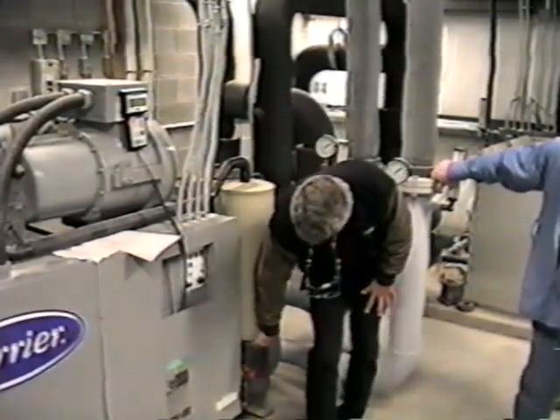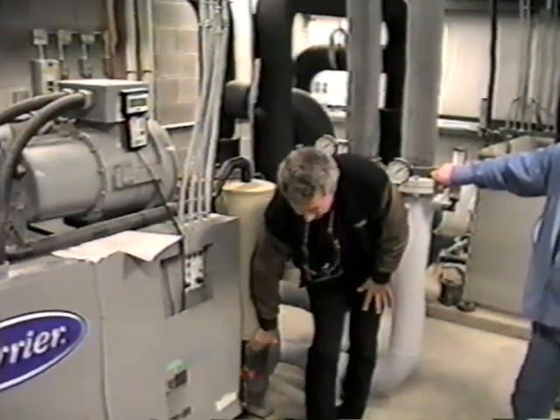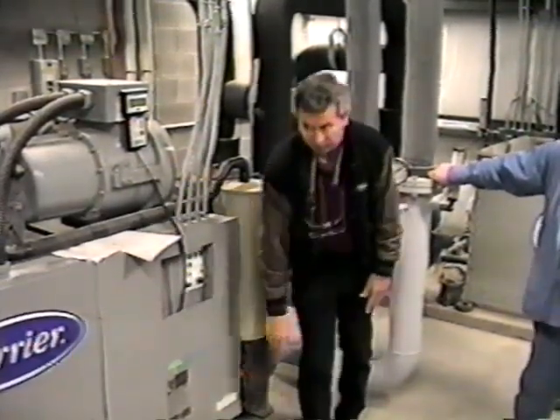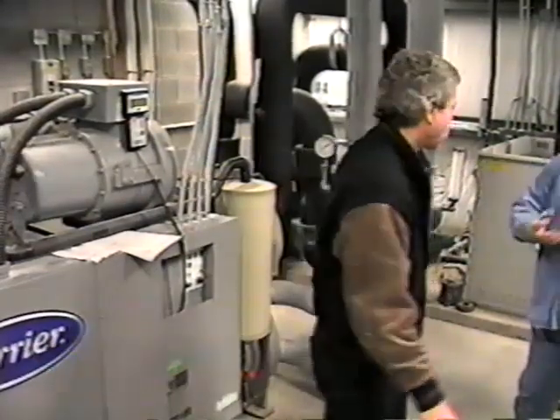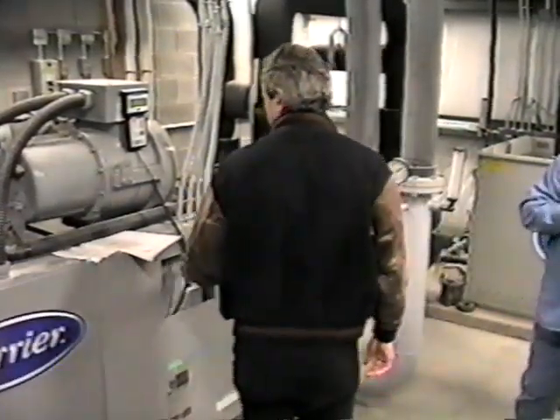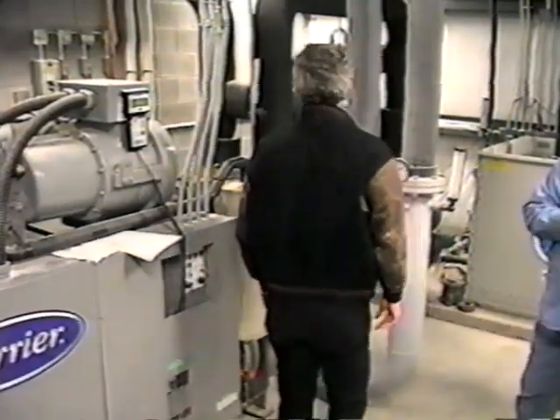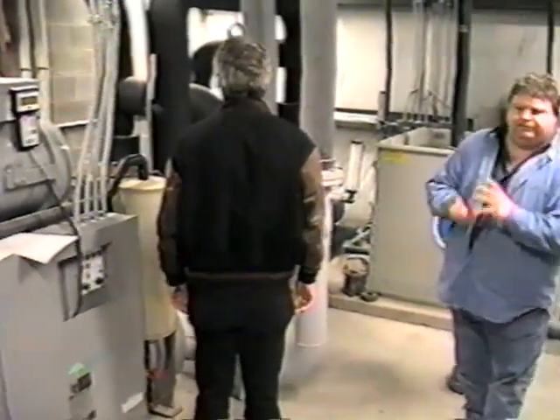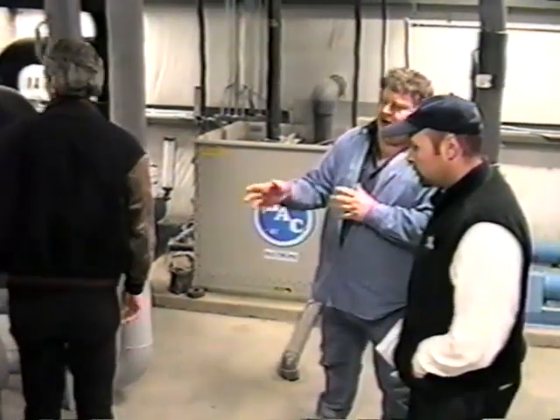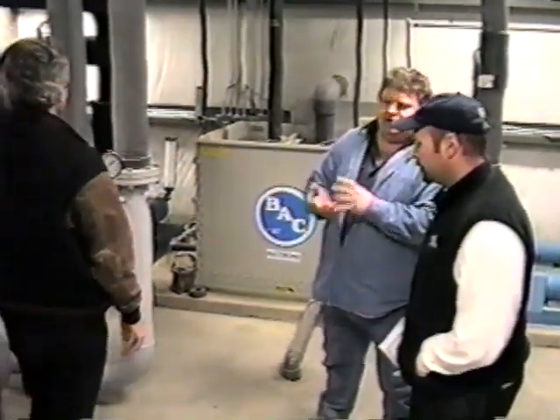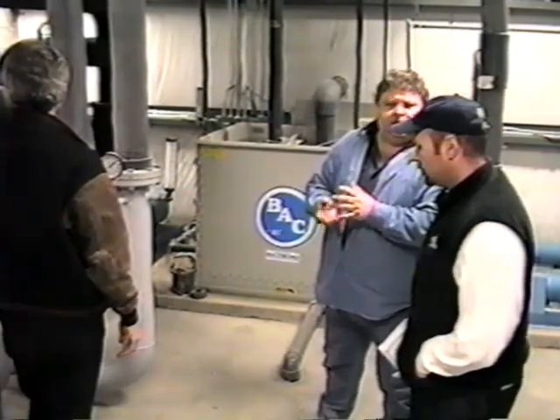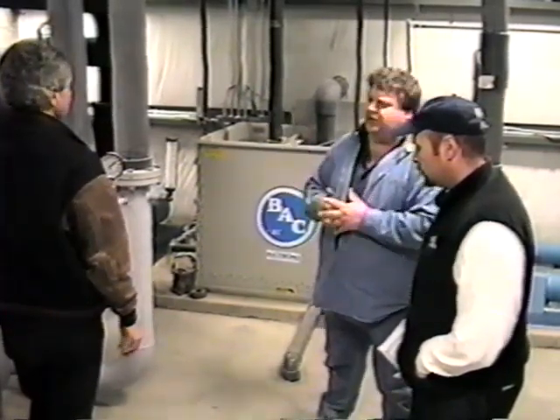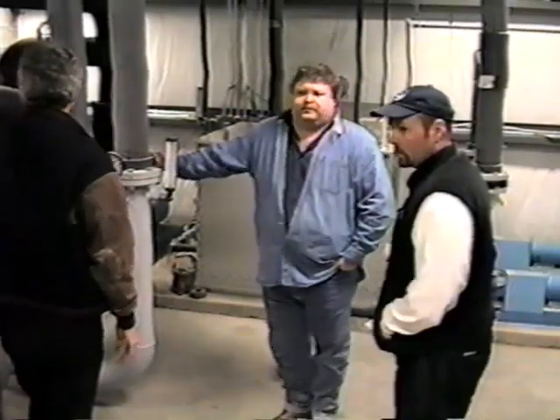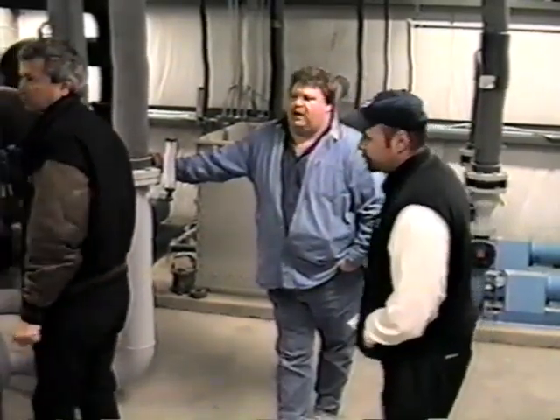The EXV is the electronic feed to the cooler, right here in each circuit. It's a motorized valve, basically, like a stepper motor type valve. The control looks at how much refrigerant it needs and opens that valve in percentage each time. It's 200 something steps, 255 or something, just getting pulses from the processor. So it fine tunes the feed rate pretty well.